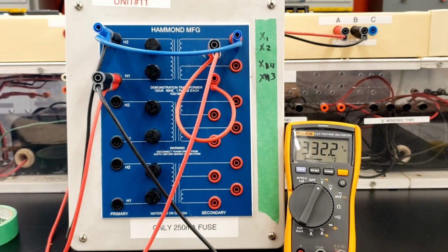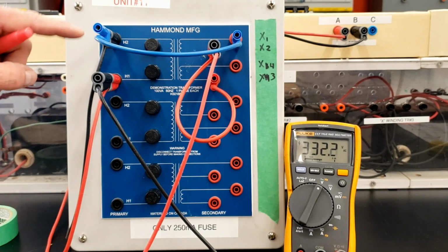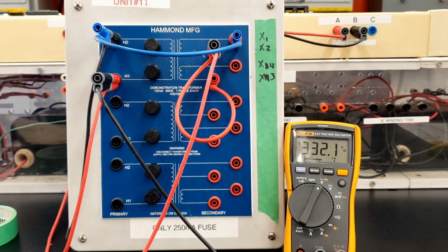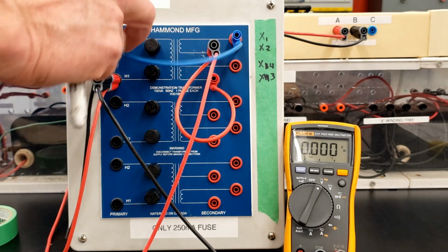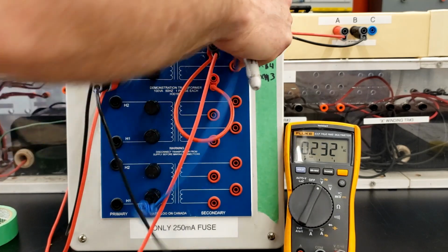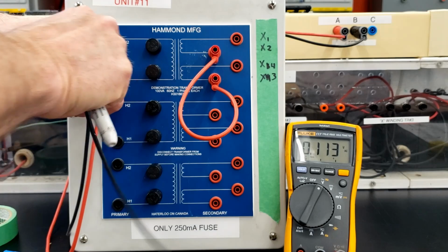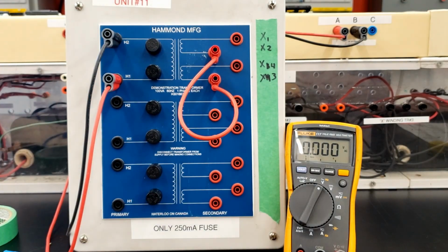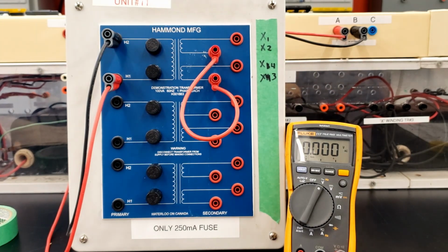Okay, so we're fairly confident that we've got all the winding terminals labeled properly now. Let's do the subtractive connection. I'm going to turn the power off, and I've got this jumper here which I'm going to remove. I'll keep my connections out for the meter here. I'm going to keep this jumper between X2 and X3. And now the jumper that I'm going to put from the primary to the secondary, the previous one I had was X1 to H2. Now I'm going to do X1 to H1.